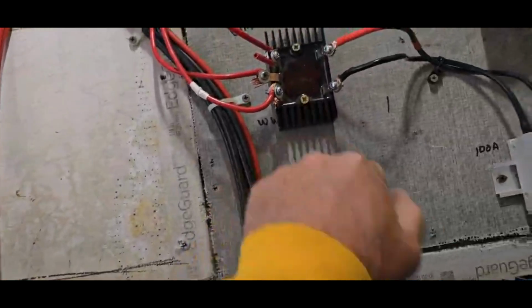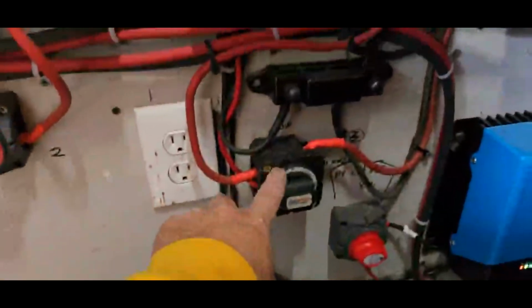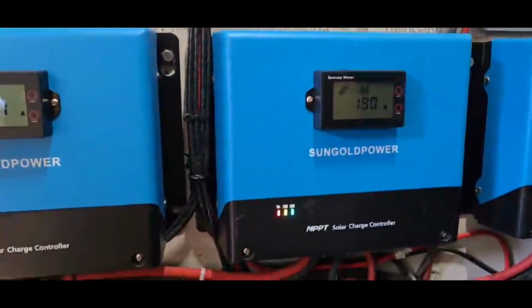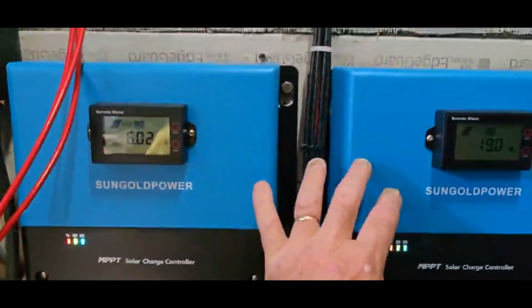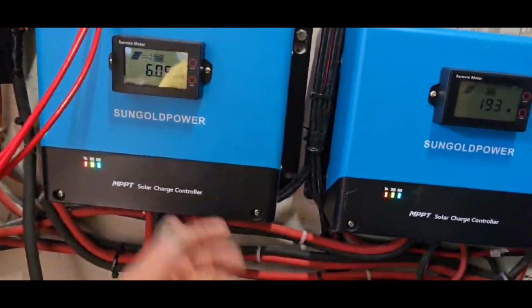This is 3-phase AC power line, number 8. It's going 300 feet, and it goes into this rectifier, which converts the 3-phase AC to DC, goes into a breaker just to shut it off, and then down into this switch, and then into this charge controller. Charge controllers limit, once the batteries are full, these notice that, and they basically shut off the output. So basically all that DC power coming in, these say, well, batteries are full, and it stops. When the batteries get low, it puts power into them.